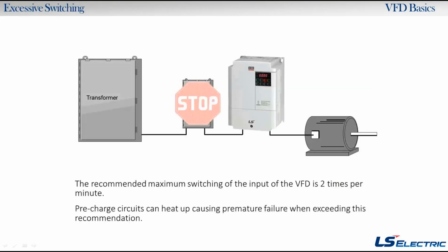So these are some other things that people ask about here and there, and that is, how often should I be turning the drive on and off? Typically, there's not too much of a problem unless you make a habit of it. So if you do make a habit of it, we recommend not switching it on and off more than 2 times a minute repetitively. That's okay if you're doing a startup and testing things out, turning it on and off, but just don't make a habit of that as a daily routine, because that's working the pre-charge circuit. So the pre-charge circuit, remember, has that resistor, and you're using that resistor every time you power up the drive. So if you turn off, then you turn on.